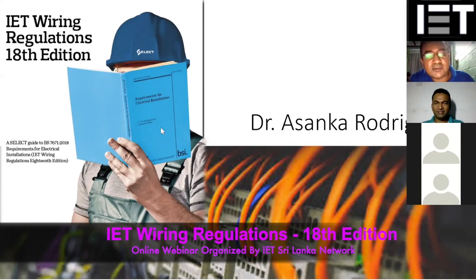Okay, thank you, Doctor. The next question is, is an auto reclosing type RCCB allowed to be installed to replace an existing RCCB in single phase domestic wiring? Yeah, it doesn't matter whether it is auto reclosing or not, but you have to comply with the basic requirements, like delta I or the sensitivity, the timing and all the other requirements. Then that's fine. The auto reclosing will reclose it a certain number of times, but the basic requirements must be fulfilled, that is the tripping time and the tripping current. If they comply with those, then there is no harm in going with the auto reclosing.